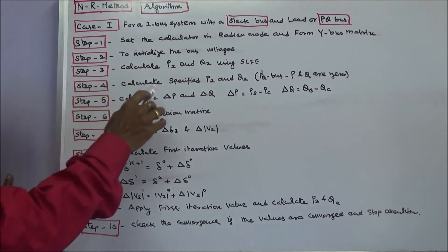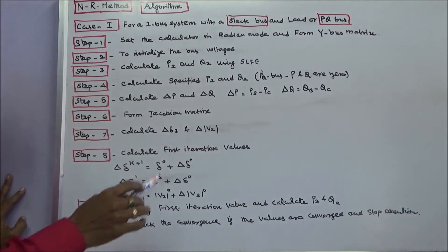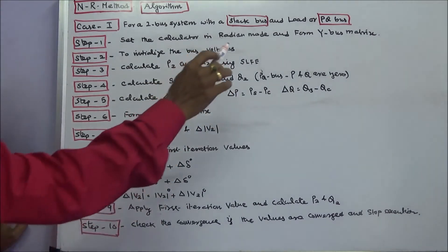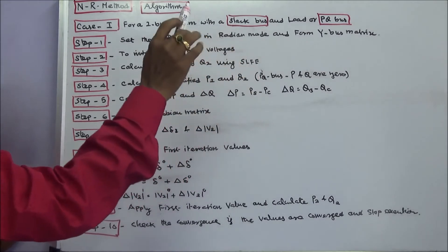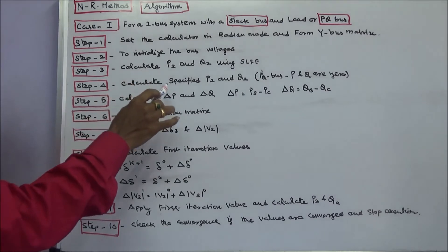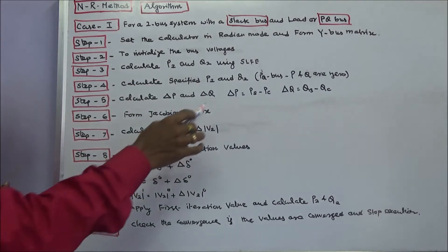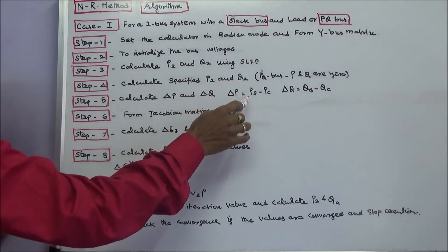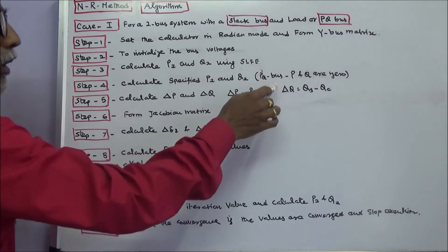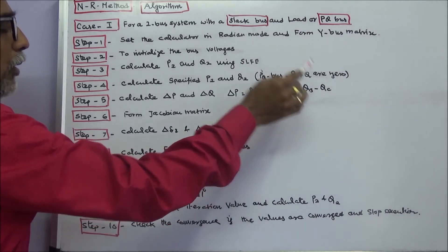Step 4: calculate the specified real power and reactive power. In the case of a load bus or PQ bus, real power generation and reactive power generation are zero. Step 5: calculate change in real power and change in reactive power. Change in real power is real power specified minus real power calculated. Change in reactive power is specified reactive power minus calculated reactive power.